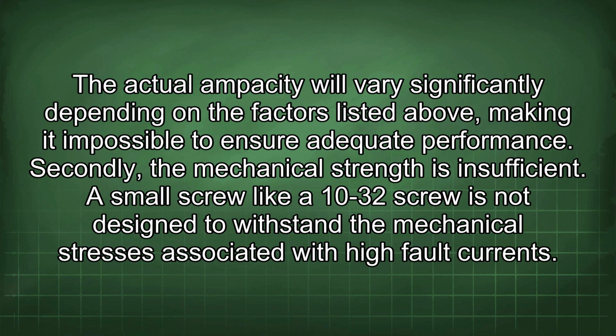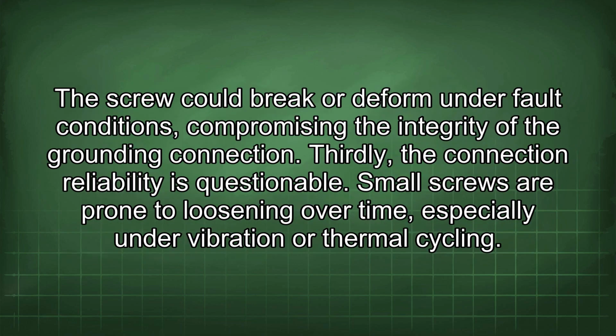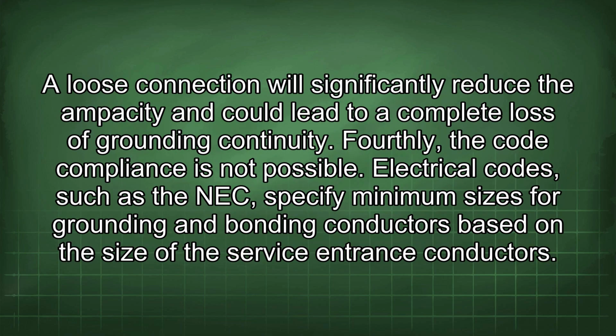Secondly, the mechanical strength is insufficient. A small screw like a 10-32 screw is not designed to withstand the mechanical stresses associated with high fault currents. The screw could break or deform under fault conditions, compromising the integrity of the grounding connection. Thirdly, the connection reliability is questionable. Small screws are prone to loosening over time, especially under vibration or thermal cycling. A loose connection will significantly reduce the ampacity and could lead to a complete loss of grounding continuity.